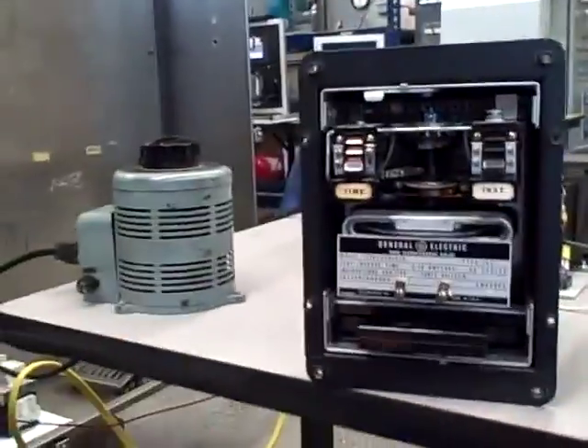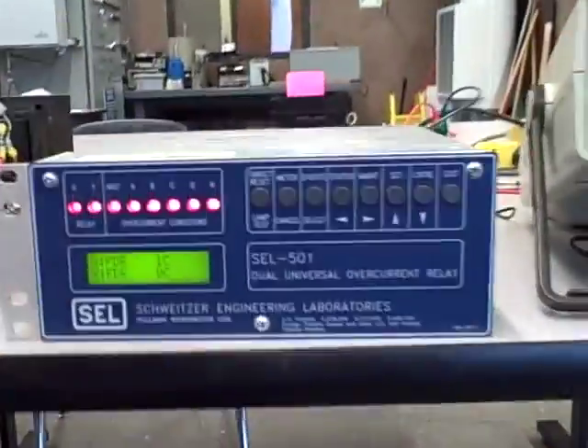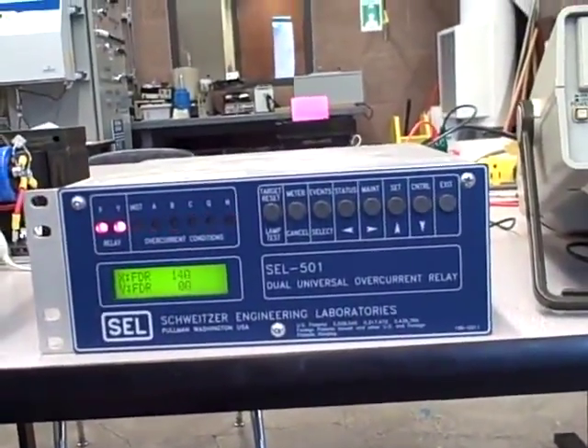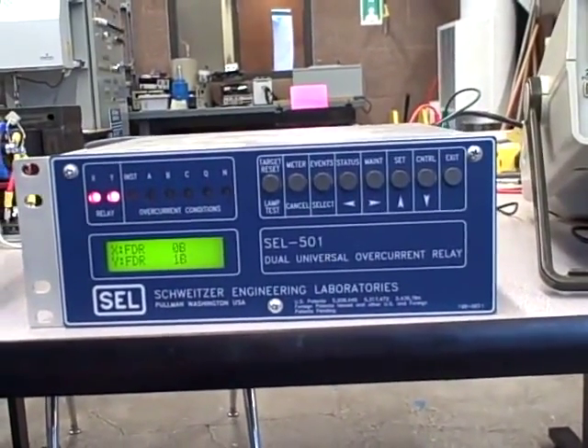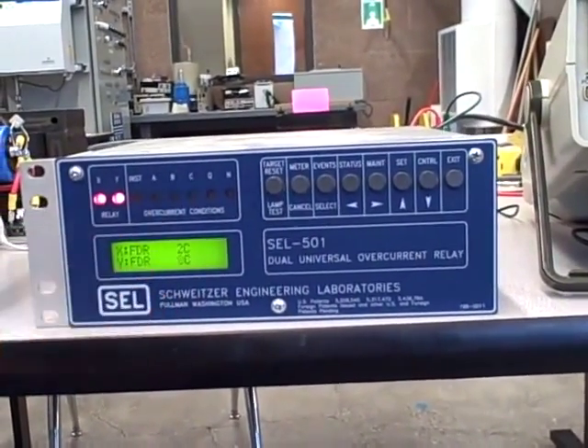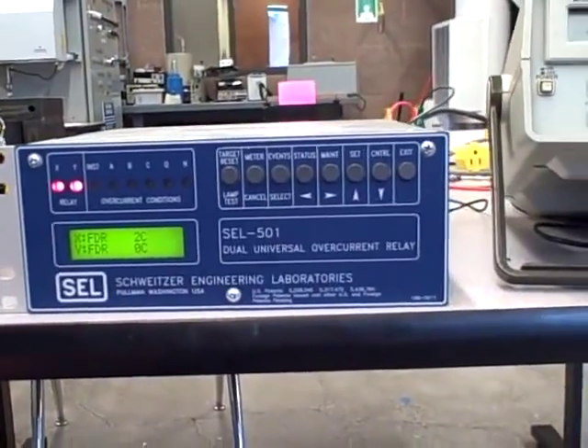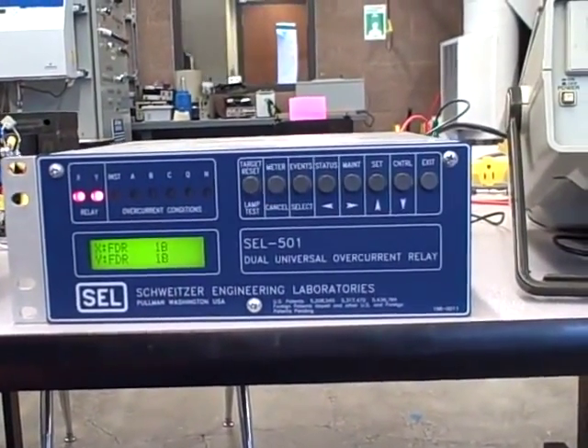So we come back over here. I'm going to do another demonstration. I'm going to reset the target here, so that's analogous to resetting the target flags on the old mechanical relay. So now everything's back to normal. I'm going to now simulate an instantaneous overcurrent condition. I'm going to put my hand on the variac.